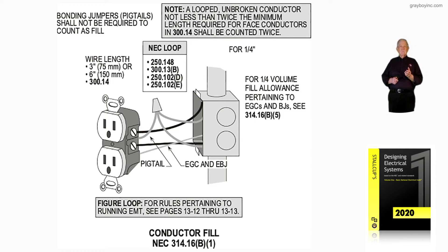Notice we have a pigtail, we have an equipment ground, and we have equipment bonding jumpers. If we have a total of four or less, there's no quarter volume added. So notice you have a receptacle, two hots (ungrounded conductors), two neutrals, and a pigtail that is spliced into your equipment ground.